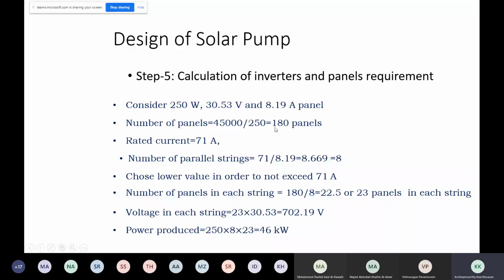Now for the pump, that civil part also you have to calculate: what is the static head, how much overhead, how much frictional losses. Based upon that, get the HP rating of the motor pump. From that, get your total electrical power requirement. We calculate it as 45,000.